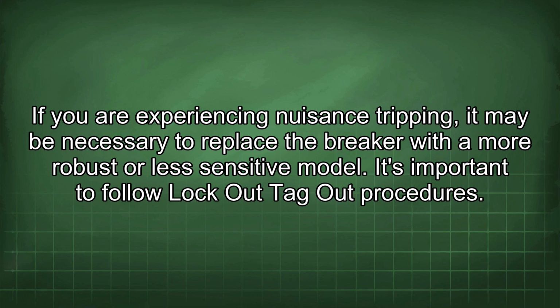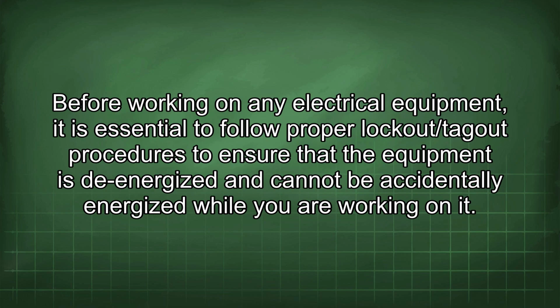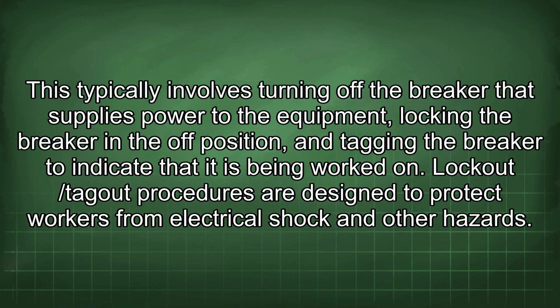sensitive model. It's important to follow lockout-tagout procedures. Before working on any electrical equipment, it is essential to follow proper lockout/tagout procedures to ensure that the equipment is de-energized and cannot be accidentally energized while you are working on it. This typically involves turning off the breaker that supplies power to the equipment, locking the breaker in the off position, and tagging the breaker to indicate that it is being worked on. Lockout/tagout procedures are designed to protect workers from electrical shock and other hazards.